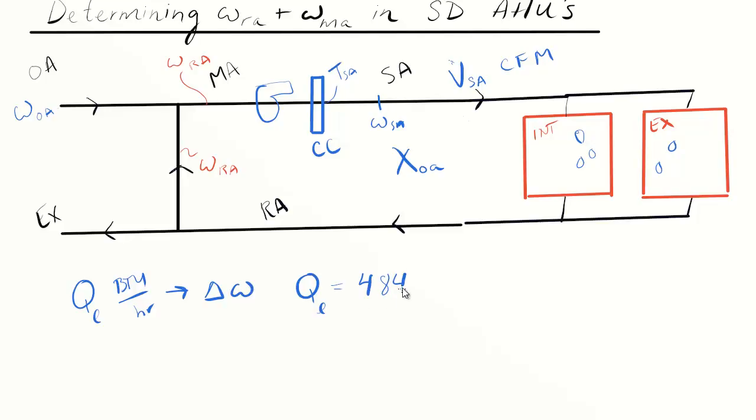We have a formulation that takes a latent load in units of BTU per hour that gives us a change in humidity ratio. I'm going to use 4840 CFM delta omega. You can think of this latent load variable as a surrogate for the amount of moisture being added to the space.